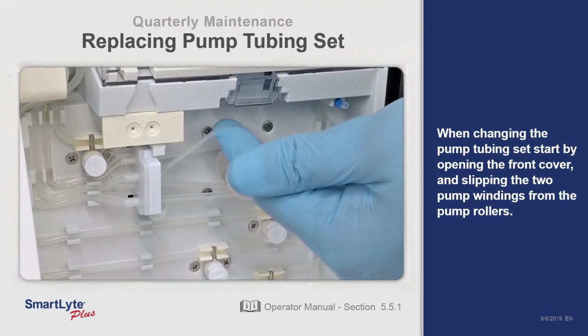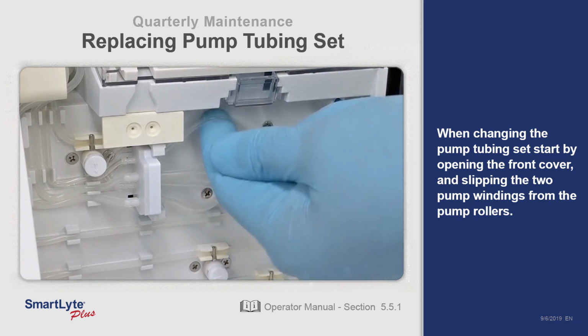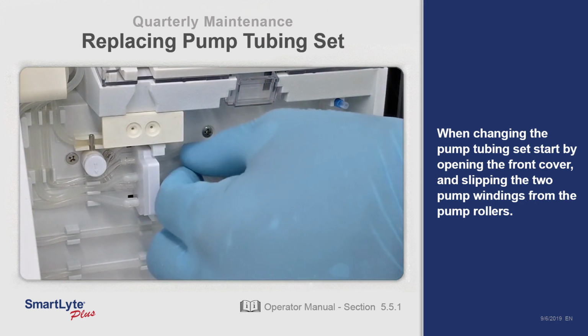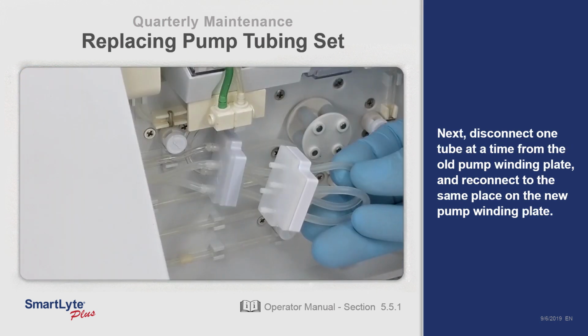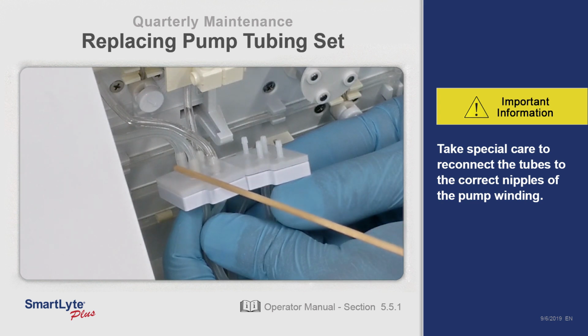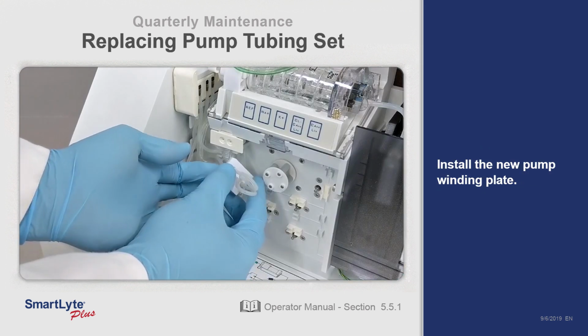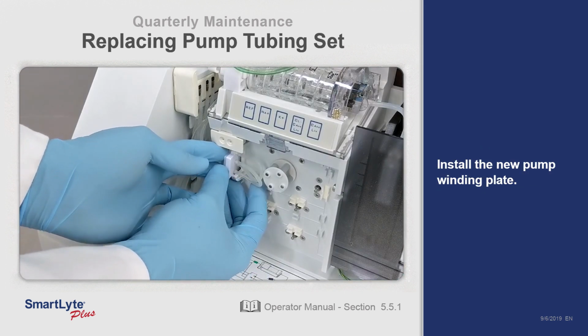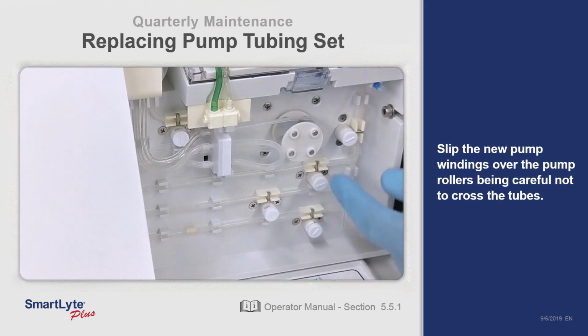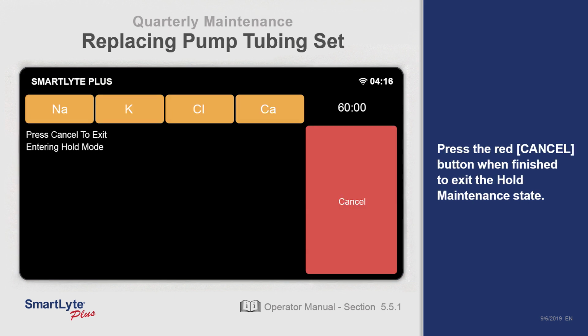When changing the pump tubing set, start by opening the front cover and slipping the two pump windings from the pump rollers. Disconnect one tube at a time from the old pump winding plate and reconnect the same place on the new pump winding plate. Take special care to reconnect the tubes to the correct nipples on the pump winding plate. Install the new pump winding plate. Slip the new pump windings over the pump rollers, being careful not to cross the tubes. Press the red cancel button when finished to exit the hold maintenance state.